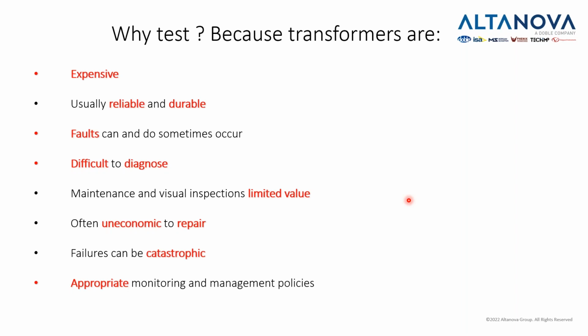So why? First of all, because the transformer is expensive and because it's usually reliable and durable, but faults can occur sometimes, and not quite often it can be difficult to diagnose the problem with the transformer. The maintenance and visual inspections have some limited value, so we have the basic tests and we have advanced tests. The most basic test, of course, is the visual inspection.